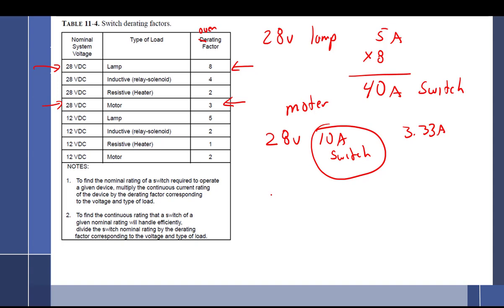It's kind of like, I've got a switch, I wonder what I could use it for. I've got a lot of motors, wonder which one I could put it with. It's almost like you bought an airplane kit from Ikea and the switch says 10 amps. So you've got to derate it. You divide by 3, so you end up with 3.33. So it's 10 amp switch divided by 3 equals 3.33 amps.